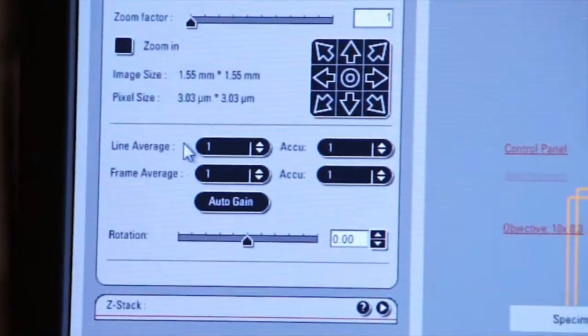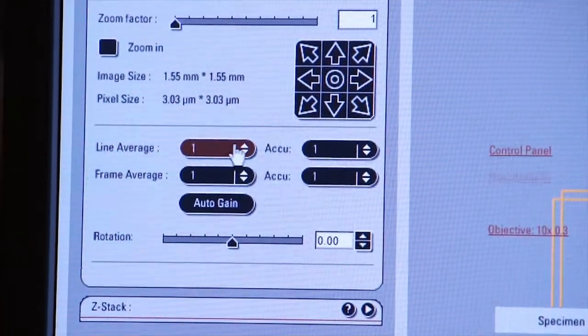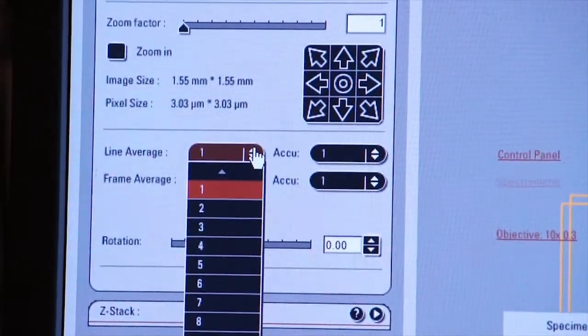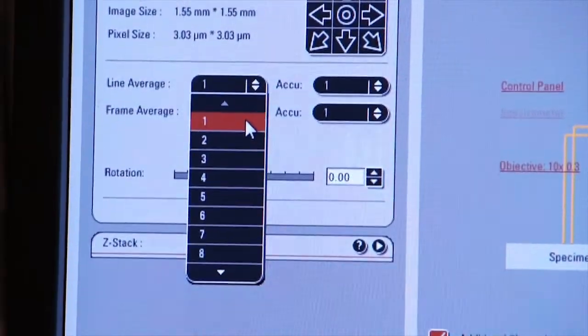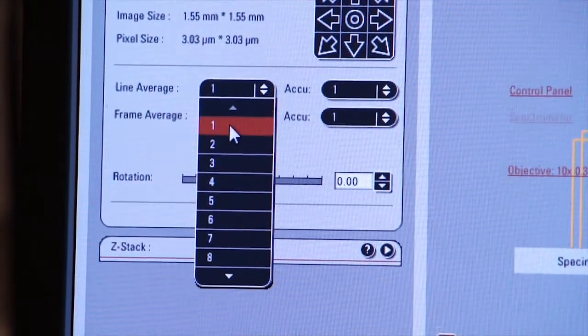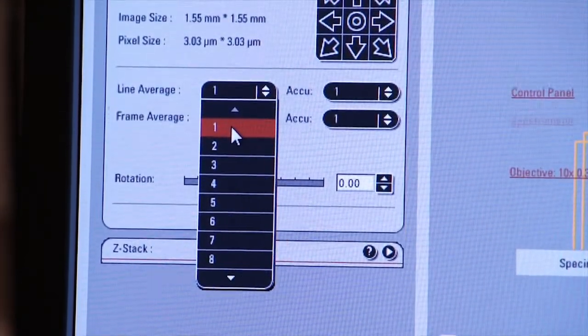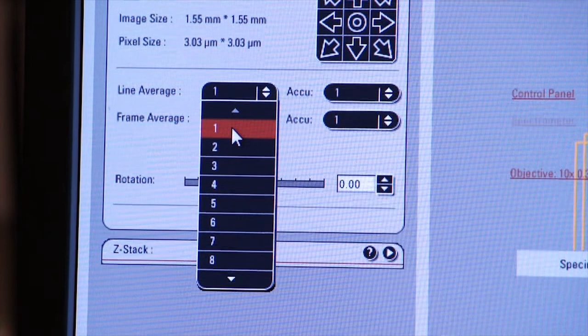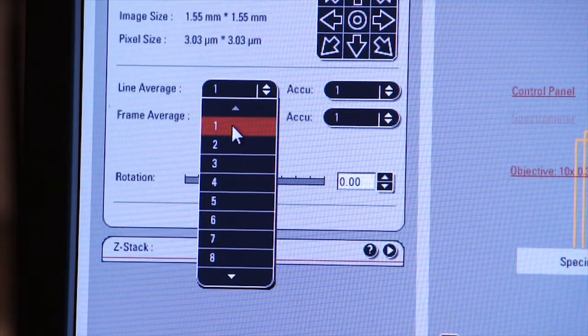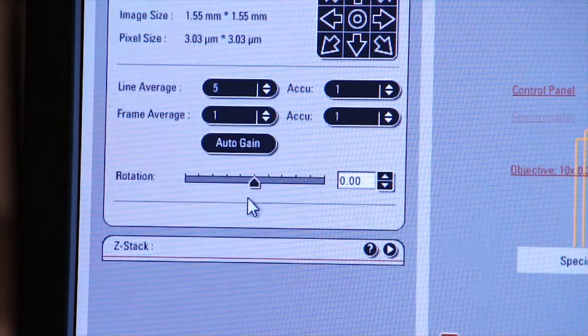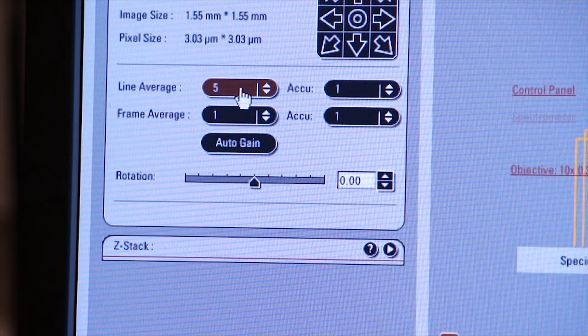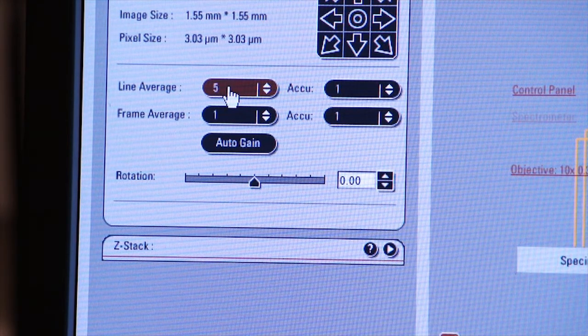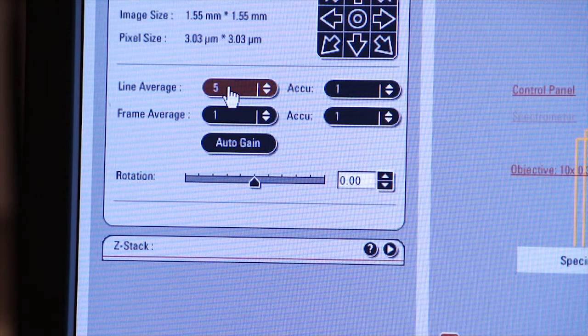Once again, we can enhance our image by doing line averaging. What is line averaging? Line averaging allows me to take more than one scan per each line, and then I average out the values of that line, and I get a cleaner, crisper, less noisy image. Normally, I would select one, but in some instances where I have noise, I may want to go to four or six and do line averaging for each line that I acquire. Remember, however, that when I increase the number of line scans that I do per line, I'm slowing down my process.